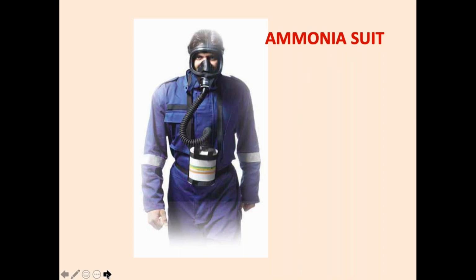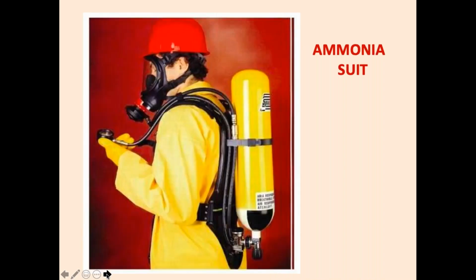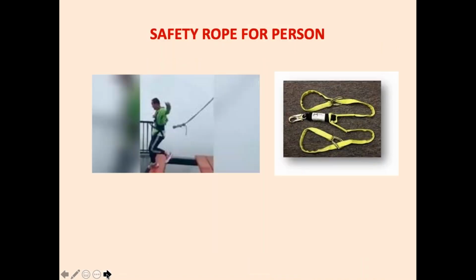If you are entering a cold room, enter with this suit, which has a breathing apparatus, so that you don't breathe ammonia and fall unconscious. And these are the space-like suits, and these are very important. When you are entering a cold room, you do not know how much ammonia has leaked. So there should be another person standing next to you outside with a long rope, and that rope should be attached to you. If you don't come out within a prescribed time of 1 minute, 2 minutes, then the other person can pull you out.